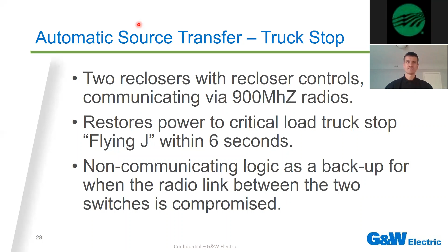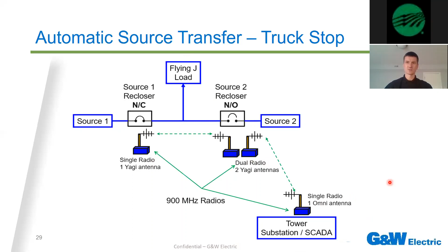This is what a simplified one-line diagram, including communication, looked like for this application. You have the critical load in the middle, a normally closed source-one recloser, meaning in a normal state source one is supplying power to that load, and a normally open recloser for source two. If you have a fault or a loss of source, the normally closed recloser opens and the normally open recloser closes to supply power. We're looking at radio communication here, and this customer also has communication back to SCADA using an additional radio at a local substation tower.